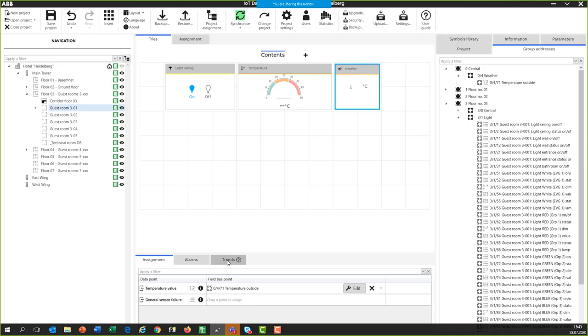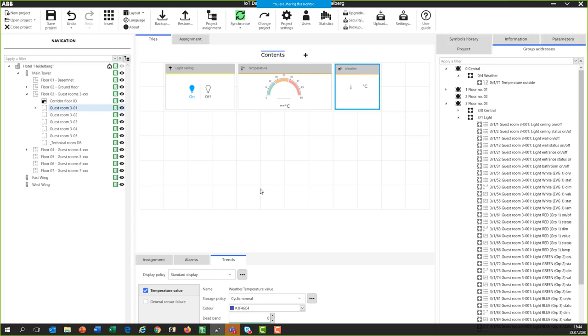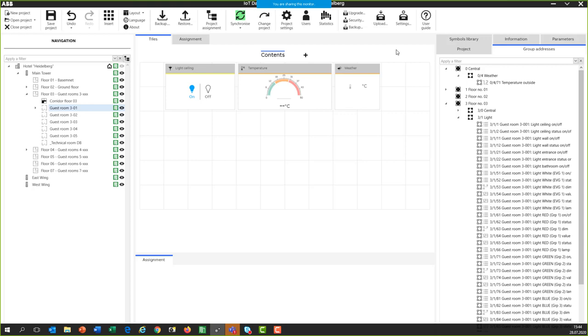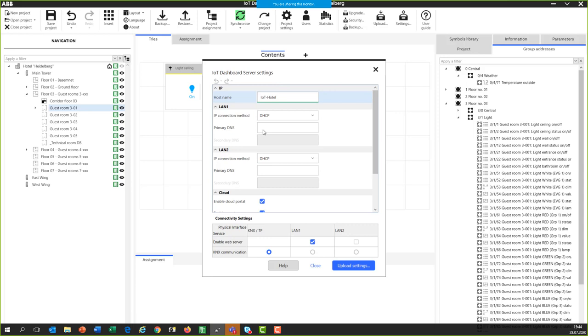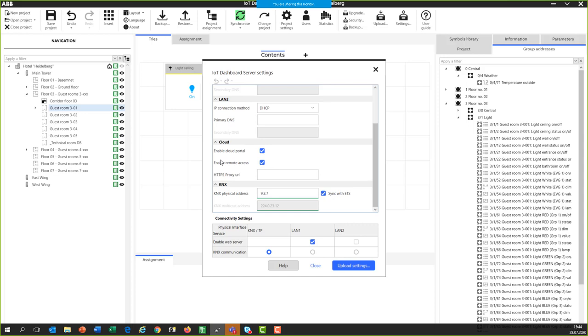I've modified the temperature and outside temperature elements: instead of only seeing the value, I want to also record the values. Click on the button 'Trends' and tick it — then all historical values are recorded. One of the first important settings is the 'Settings' button. Under LAN communication, we must tick 'Enable Cloud Portal' and 'Enable Remote Access' — this is needed later if we want to register the device in the My Building Portal. Make sure these two fields are ticked, then upload the settings.